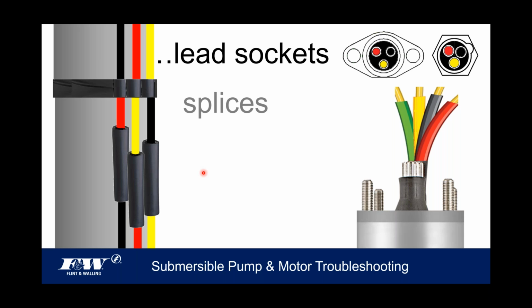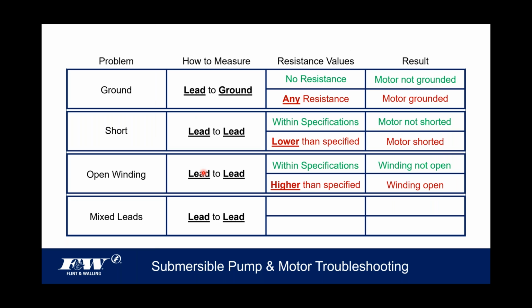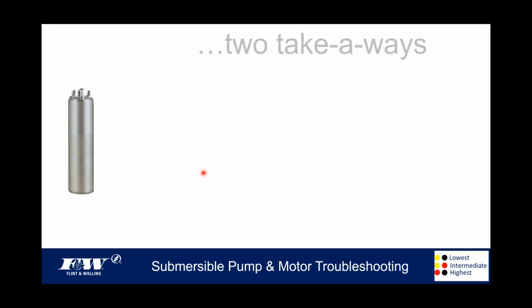And sometimes these wires, they get old, the color fades. You can't tell one color from another. Although with my multimeter, I could tell you what every one of those wire colors are. If they were all black, I could tell you which one should have been red and which one should have been yellow, because I know which two are the lowest values, I know which two are the intermediate, and I know which two are the highest. And so, again, when you come in and you're within higher and lower, that's always going to be an indication of mixed leads.